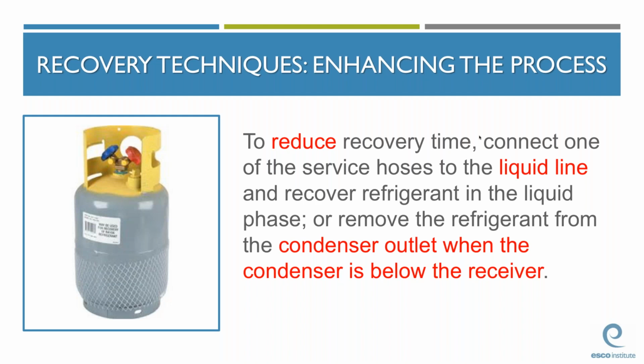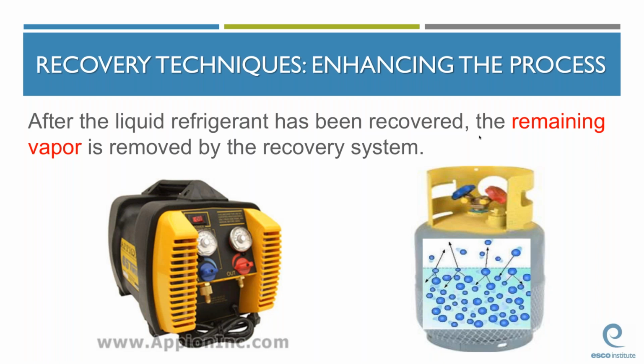It's also important that you let your students know that once all of the liquid has been recovered, they're not done, as the system still contains vapor refrigerant. This vapor refrigerant must also be recovered. On larger systems, the amount of vapor refrigerant left in the system can be pretty significant.